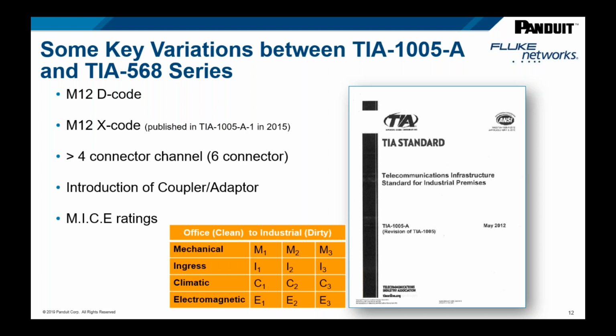So what sets TIA 1005A apart from the commercial standard? The main thing is recognizing the dynamics of the plant floor environment, and really the adoption of the MICE criteria when evaluating that plant floor. MICE is an acronym for things commonly looked for by a design engineer out on the plant floor: it covers Mechanical, Ingress, Climate and chemical, and Electromagnetic. This is a big difference from the commercial standard, which is much more of a static environment.